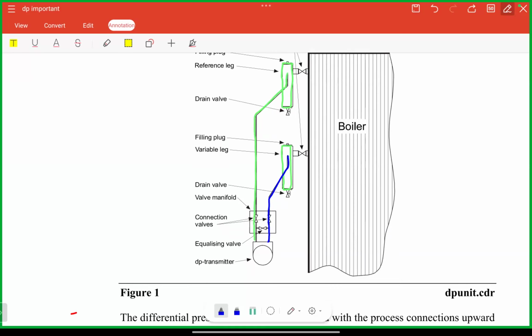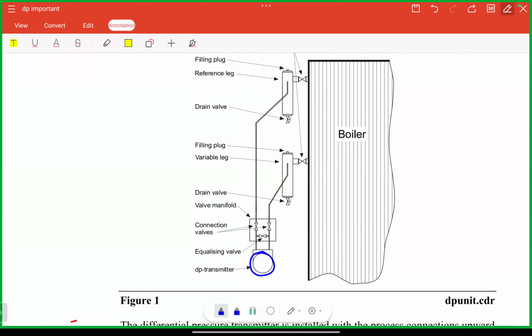Then there will be isolation valves in case you need to repair, replace, or calibrate your DP transmitters. On each condensing pot, there will be drain valves provided. During the initial commissioning and calibration process, you need to equalize the pressure across your DP transmitter. So in between, an equalizing valve is also provided. And finally, it is your DP transmitter. Clear with this general arrangement?